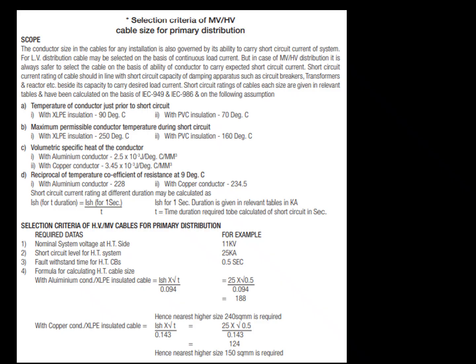Now we are learning selection criteria for medium and high voltage cables. The conductor size in the cable for any installation is always governed by its ability to carry the short circuit current of the system. For LV distribution, cable may be selected on the basis of continuous load current, but in case of medium voltage and high voltage distribution, it is always safer to select the cable on the basis of its ability to carry expected short circuit current. Short circuit current rating of cable should be in line with the short circuit capacity of damping apparatus such as circuit breaker, transformers, and reactor, beside its own capacity to carry desired load and current.